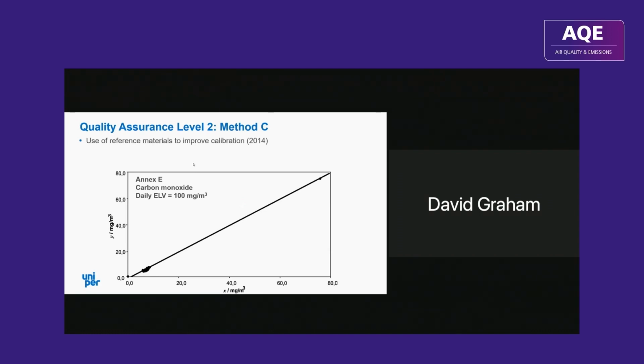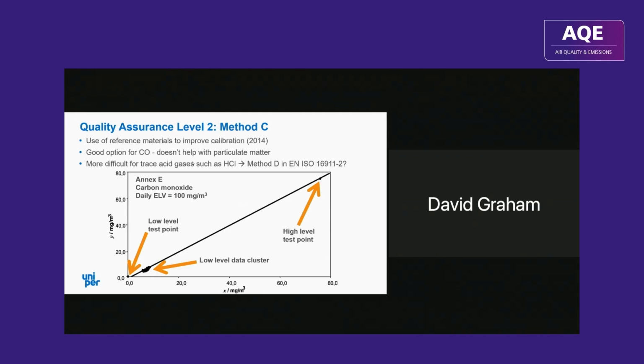allowed the use of reference materials to improve the calibration. Of course, the reference materials have to be of really good quality. So this addresses a situation where you have a low-level data cluster. You can put in a zero and a span point effectively. That's a really good option for CO, because there may not be appreciable levels when you're doing the QAL2 measurements, but it doesn't really help with particulate matter, since there are no milligram per meter cube reference standards for particulate.